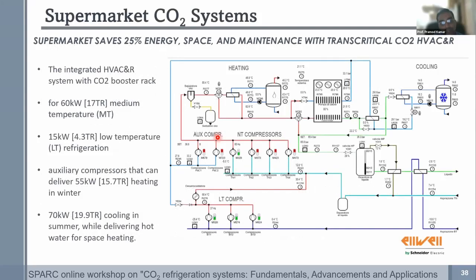So from an Indian perspective, CO2 now has the potential to replace your entire supermarket with just one system. You can have one system with multiple levels of ejectors and different levels of cascade compressors mounted on a rack in very compact spaces, and you can now have refrigeration, air conditioning, deep freezing, as well as heating, all in a single system. So it's just possible in one system. This is really the advantage, and this is where the whole world is going.